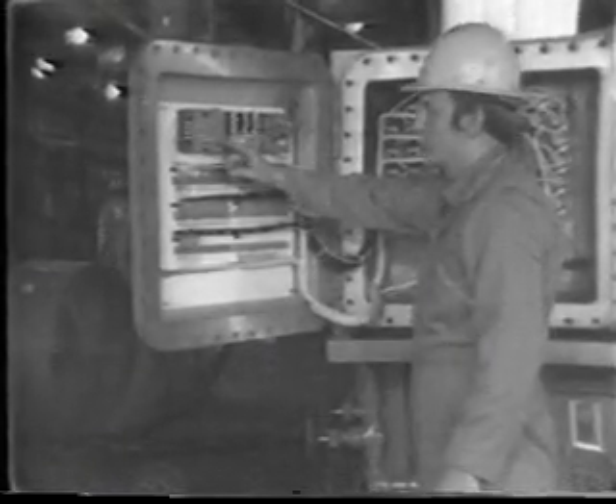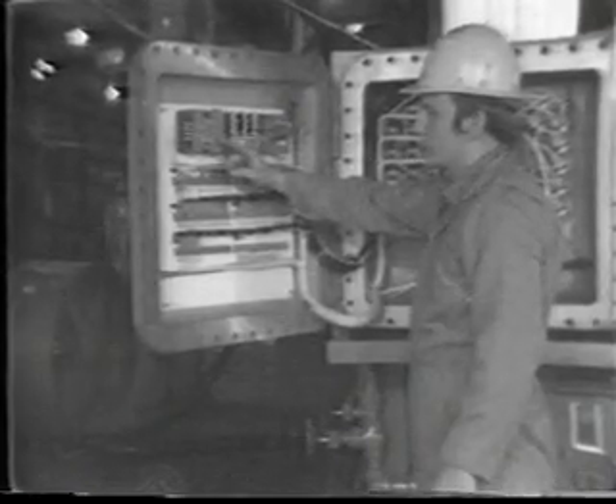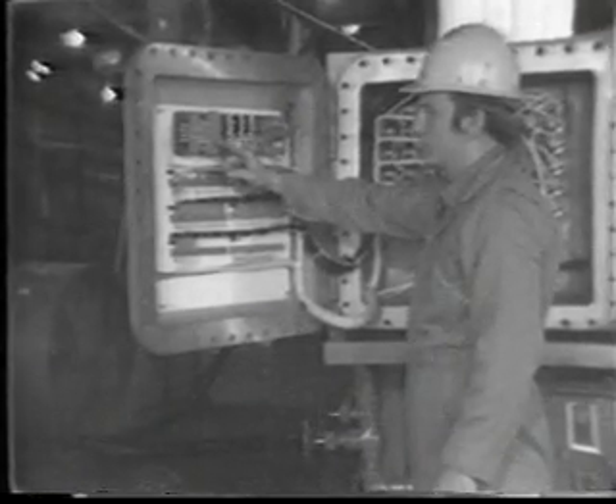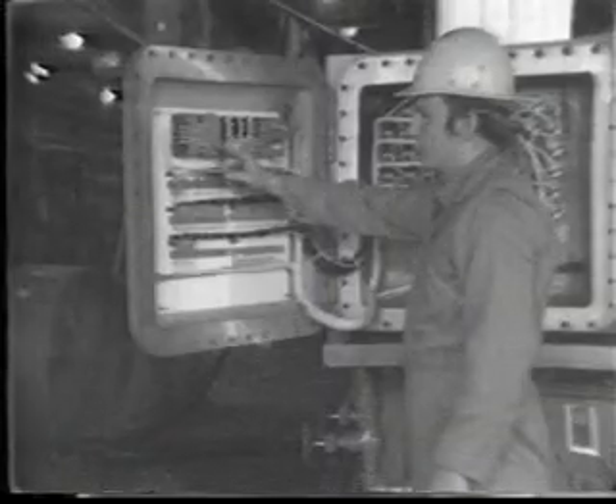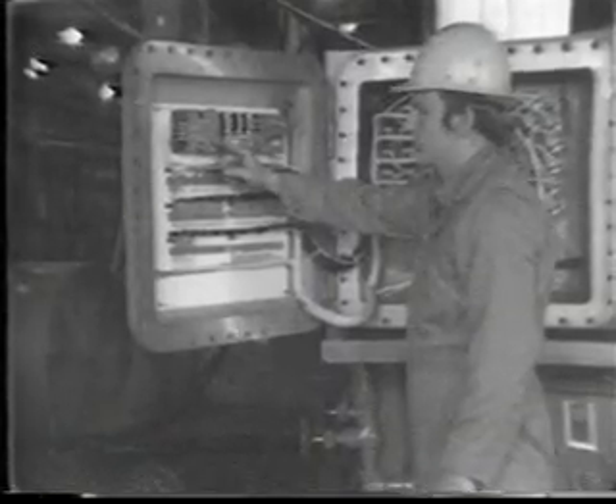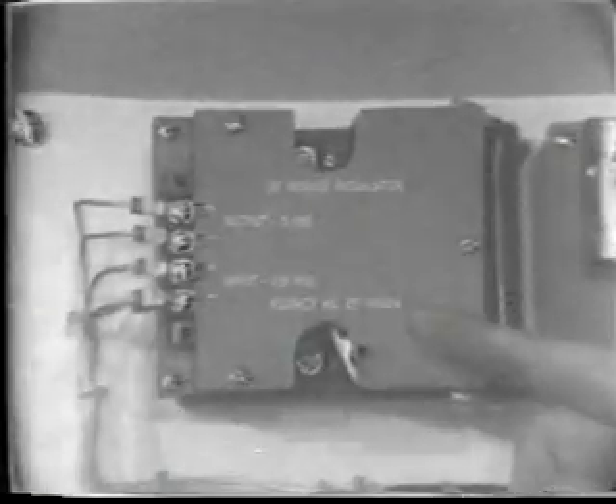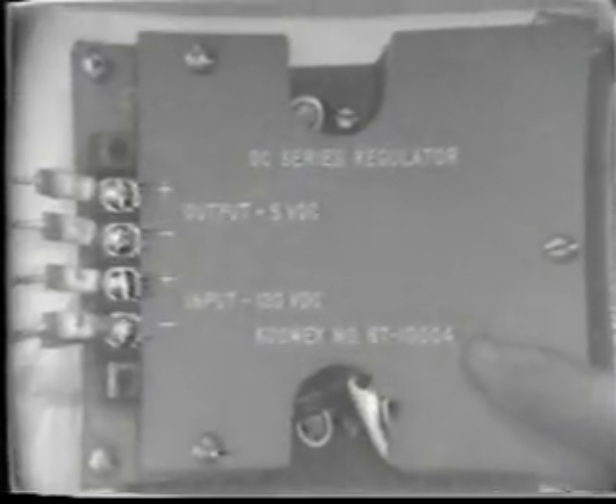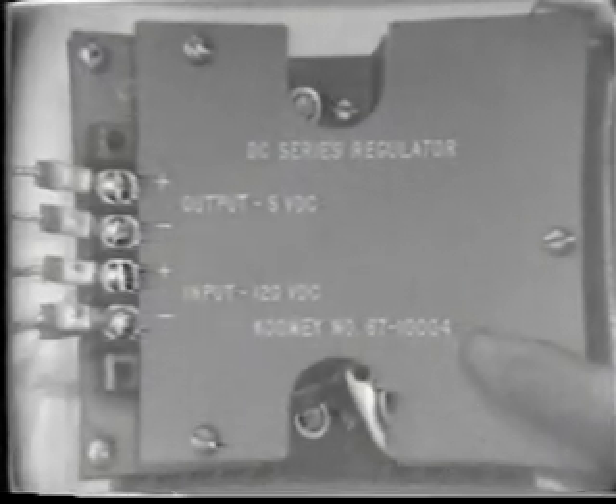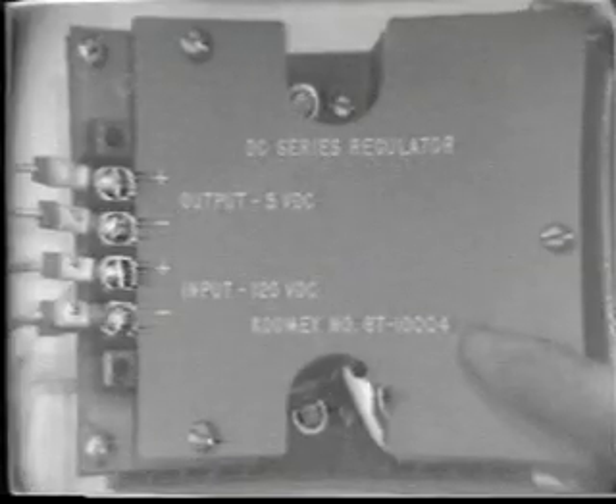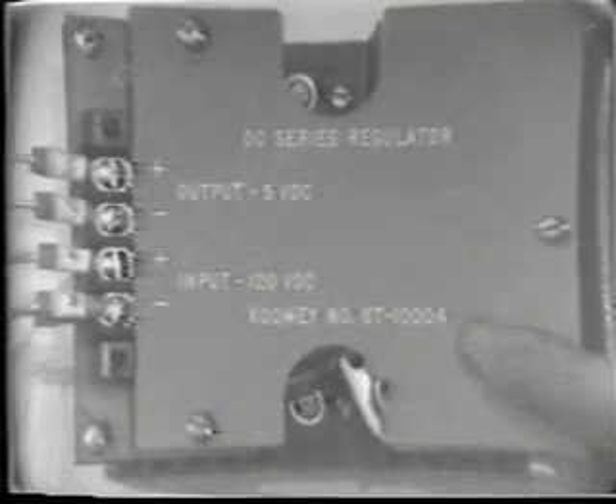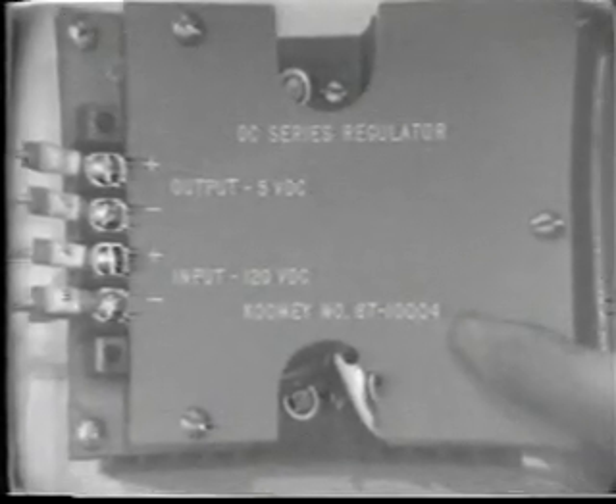Apart from the power pack, there is a DC series regulator which is used to supply the necessary DC current to the transducers. This regulator is located in the left-hand explosion-proof junction box on the hydraulic control manifold. Voltage output of this regulator varies from system to system. However, the voltage is clearly marked on the cover plate for the regulator. Another component of the electrical system is the solenoid.